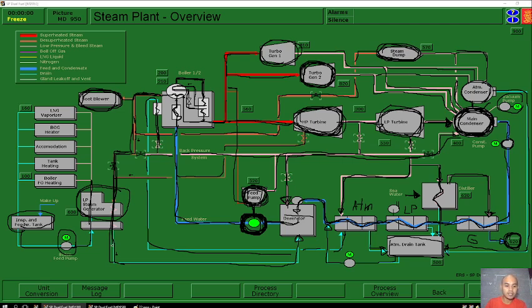So the steam in here is the one that is creating steam on the water side. So the heat of this steam will make the water in here boil, and then you will be creating a low pressure steam. So those low pressure steam is used for heating the fuel oil for the boiler, FO heating.